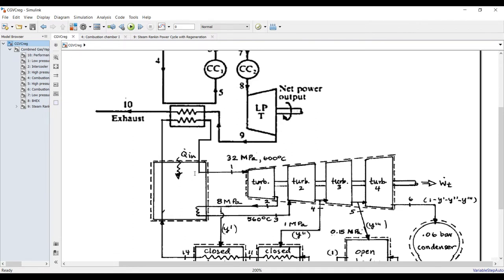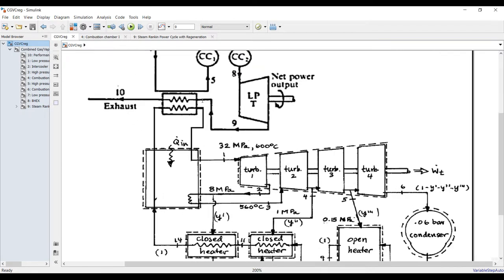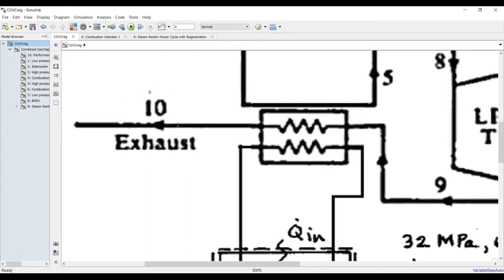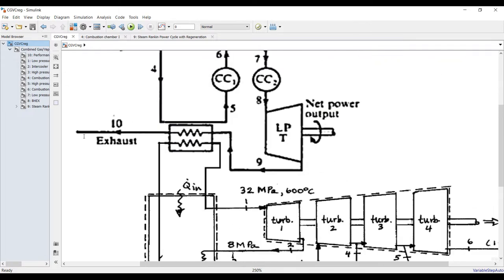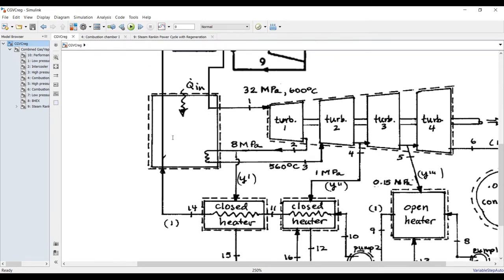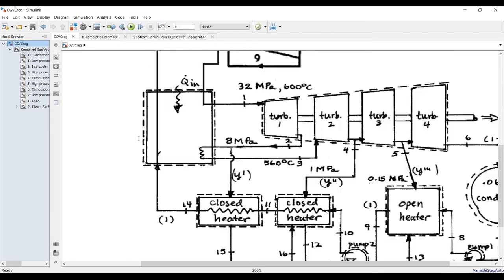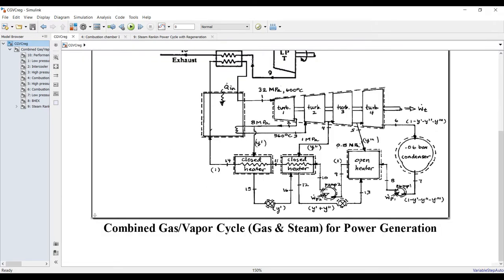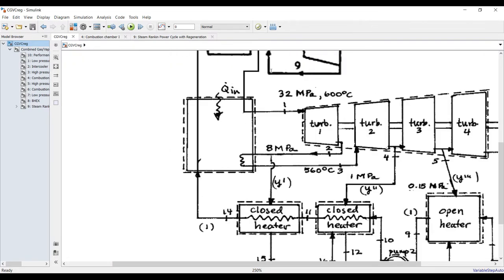The exhaust stream from the low-pressure turbine is the main thermal driving power for the steam or bottoming cycle through the boiler heat exchanger unit. We can also utilize this exhaust stream for an organic Rankine cycle, thermal desalination, process heating, or whatever the system design requires. The boiler heat exchanger receives the top-cycle pressure, and the boiler outlet temperature is calculated from the upper cycle.